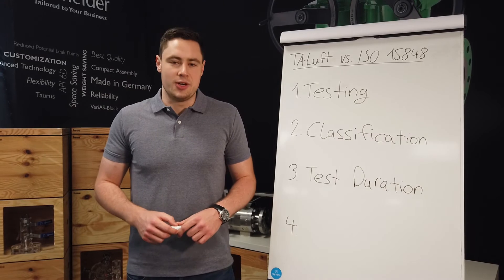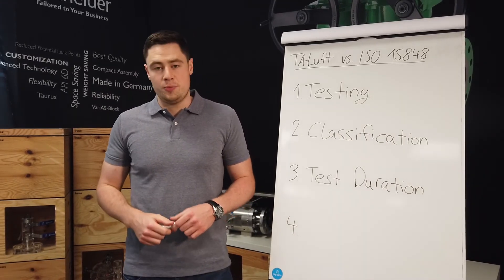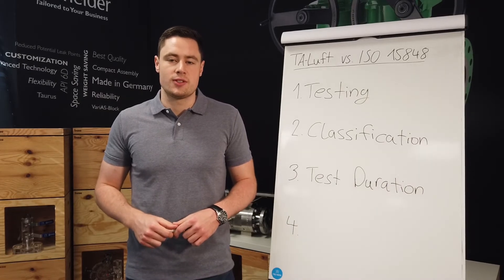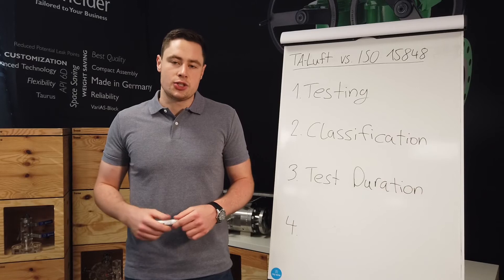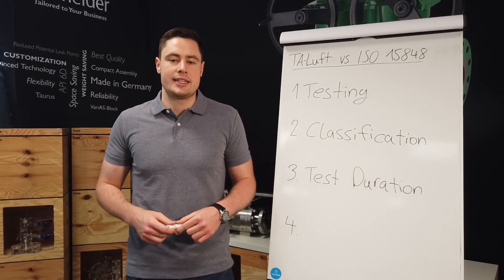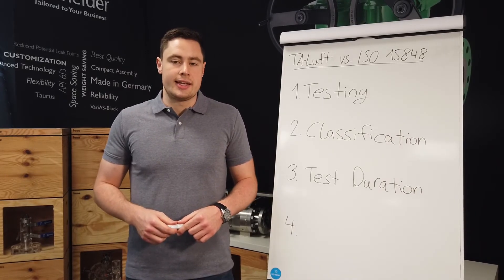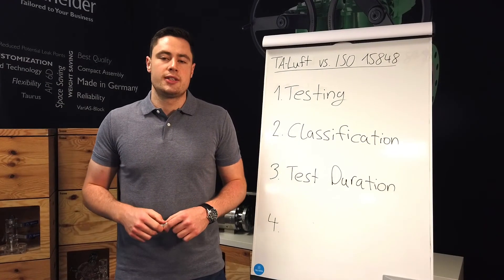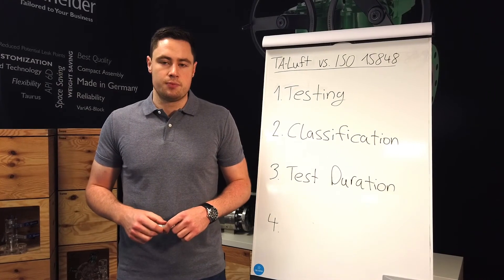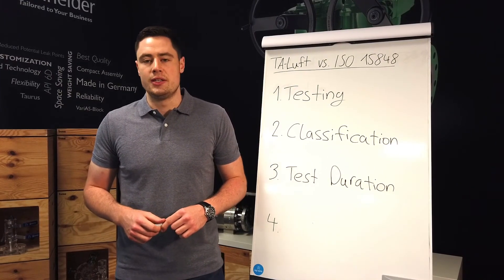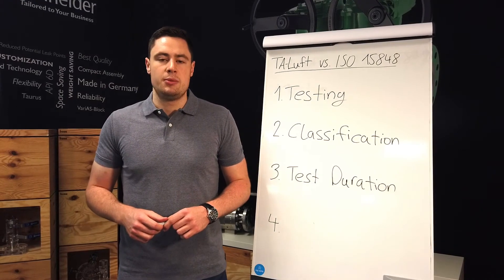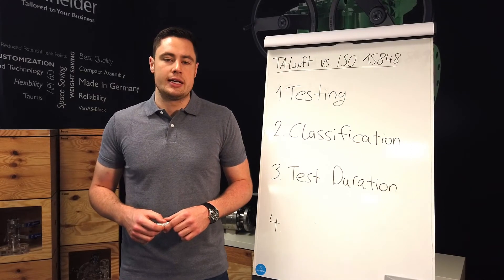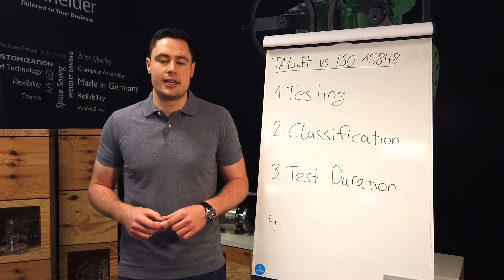The ISO 15848 consists of two parts. The first part is a classification system and qualification procedures for tightness testing of industrial valves. A distinction is made here between three tightness classes: A, B and C, where Class A has the smallest environmental leakage. Part 2 is a production acceptance testing of industrial valves — only products that have successfully completed the first part of the test may be subjected to this test. Leakage is tested at room temperature without mechanical effects, utilizing a helium leak detection test.